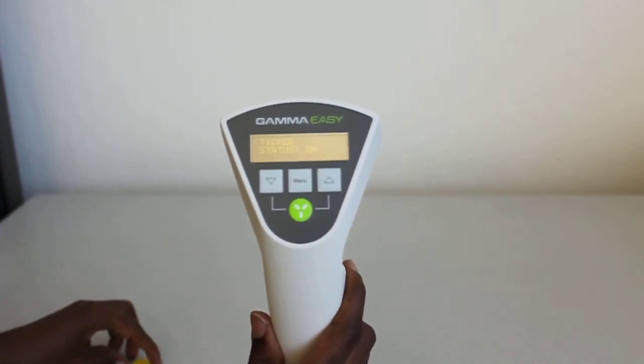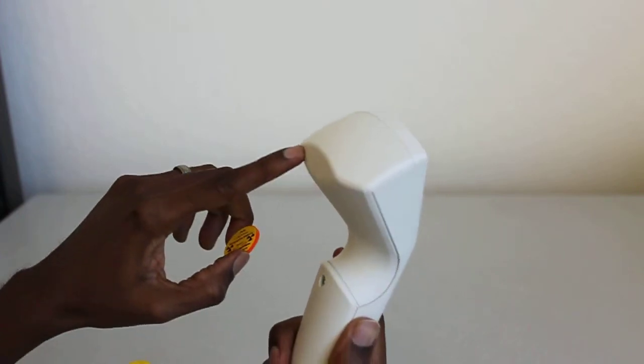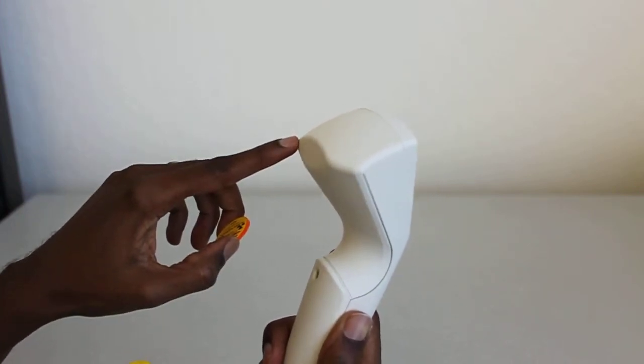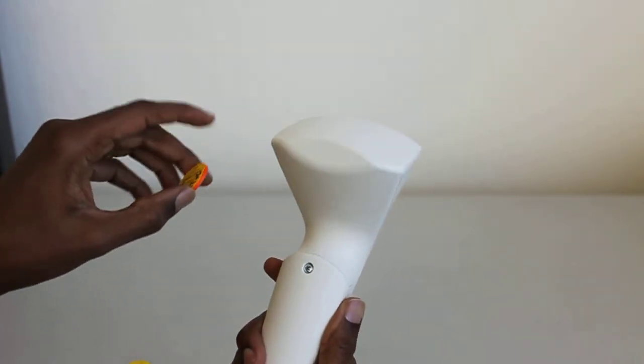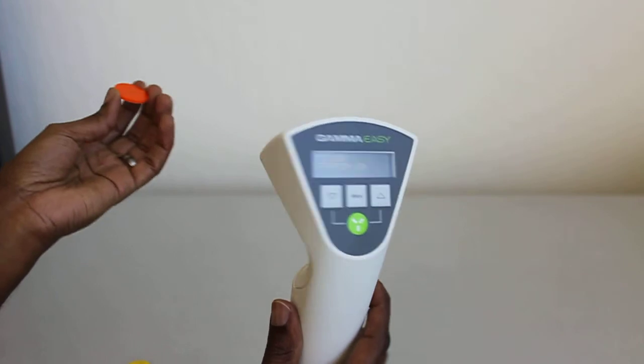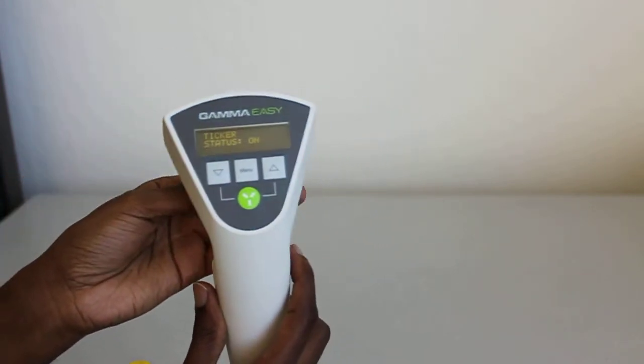And let's see what it does with the Cobalt-60 source. So the sensor is actually in the middle here. I think it's sitting horizontally across this way. So if we place the gamma source pretty much anywhere, because it goes through plastic material pretty easily, then we should see the measurements shoot up.